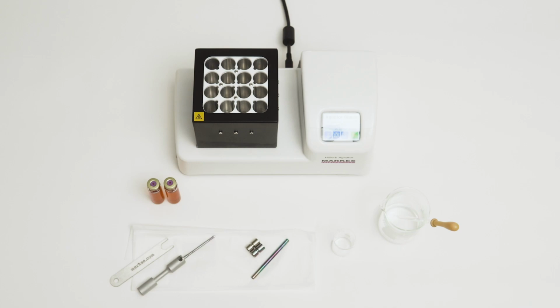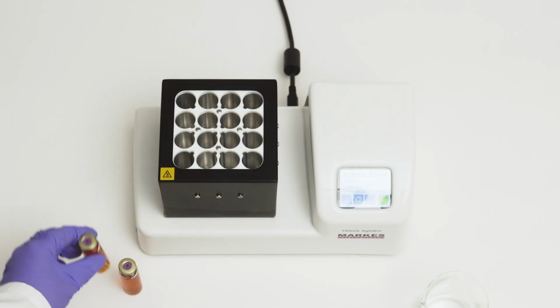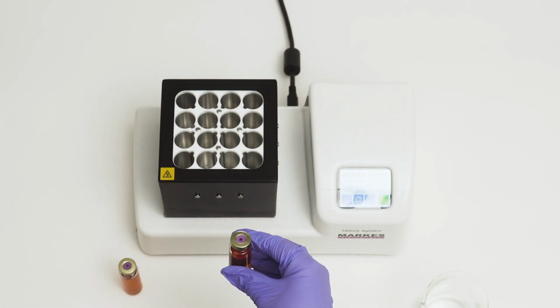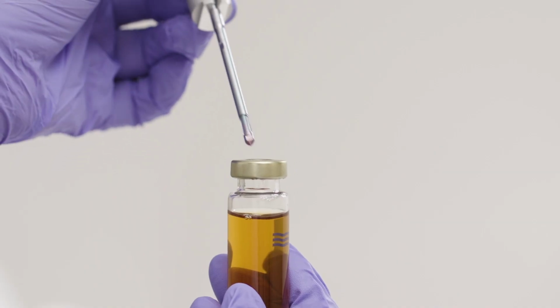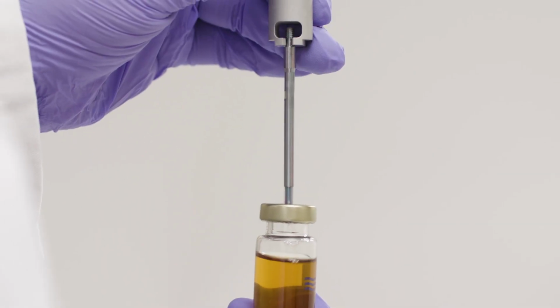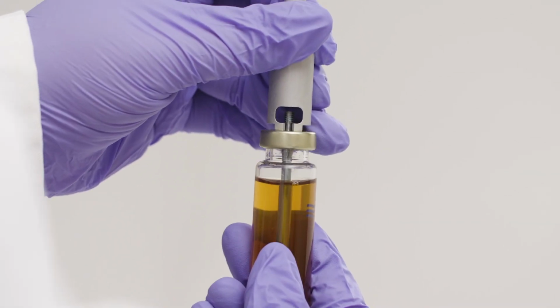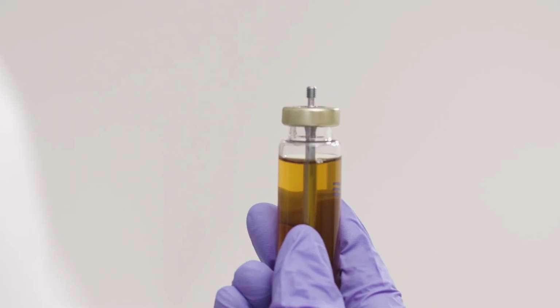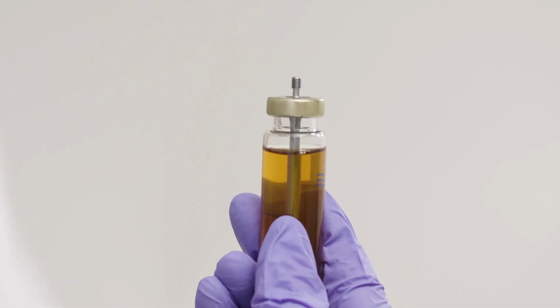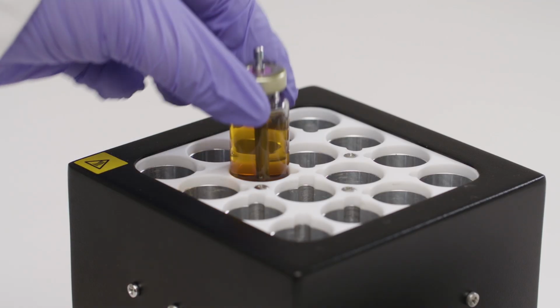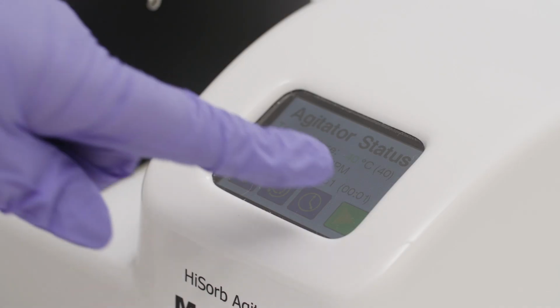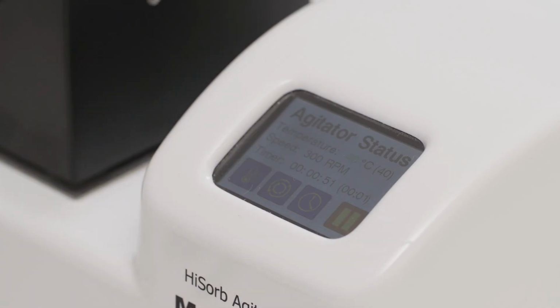Place your sample in a 20 ml or 10 ml vial, sealed with a crimped HiSorb septum cap. Start by placing your conditioned probe into the sealed vial. Ensure you only handle the probe with gloved hands or the HiSorb extraction tool to prevent contamination. To mix and heat the sample, use the HiSorb agitator to facilitate extraction.